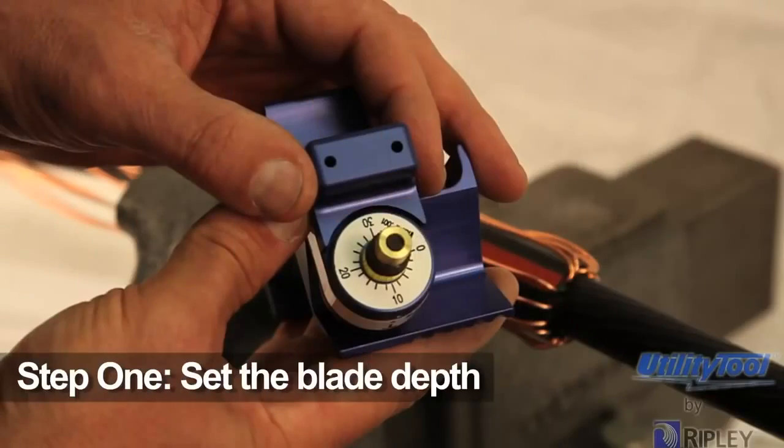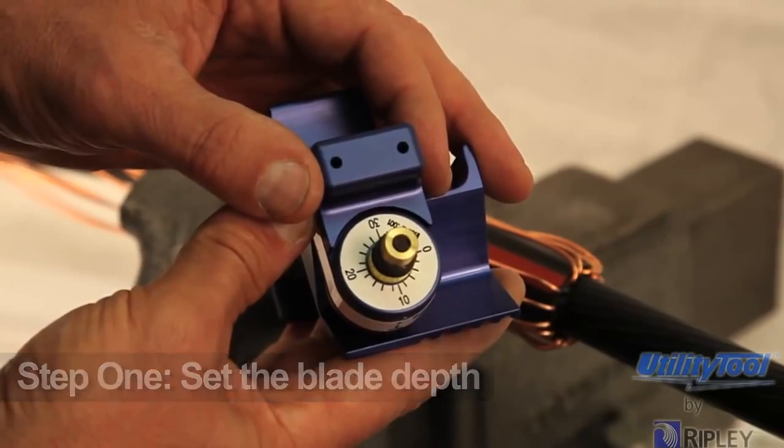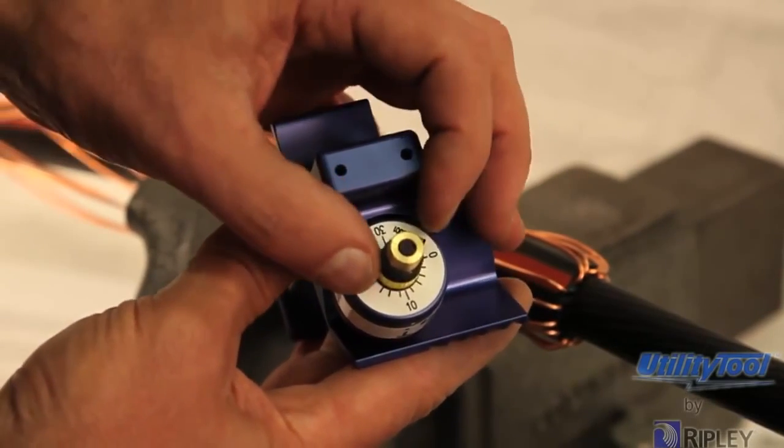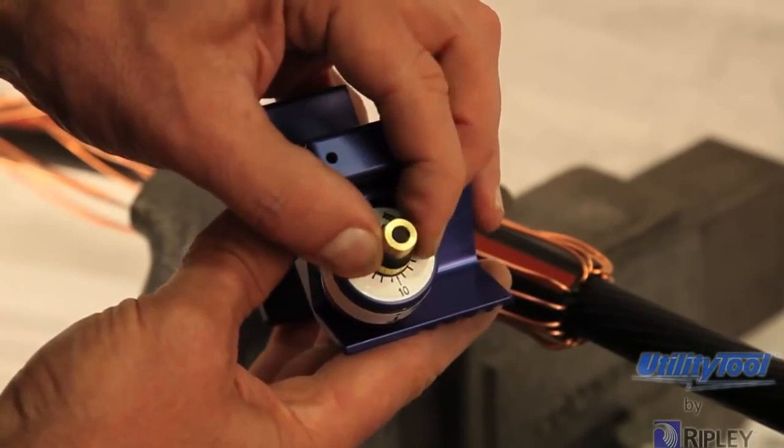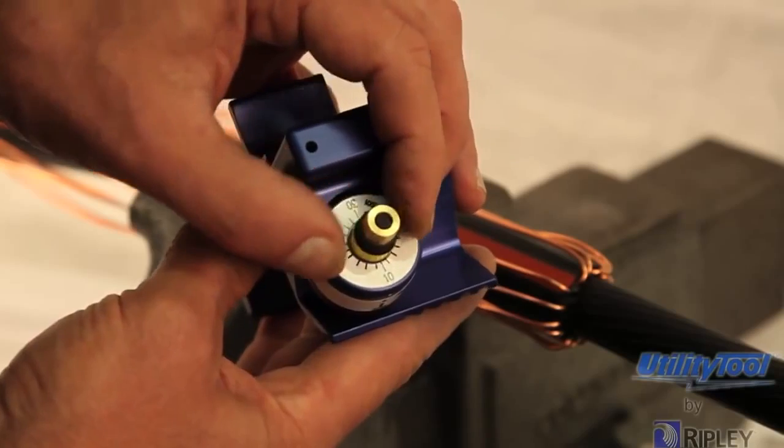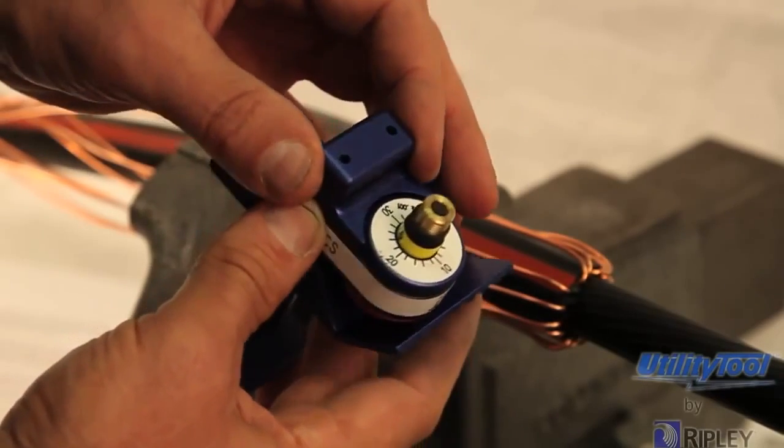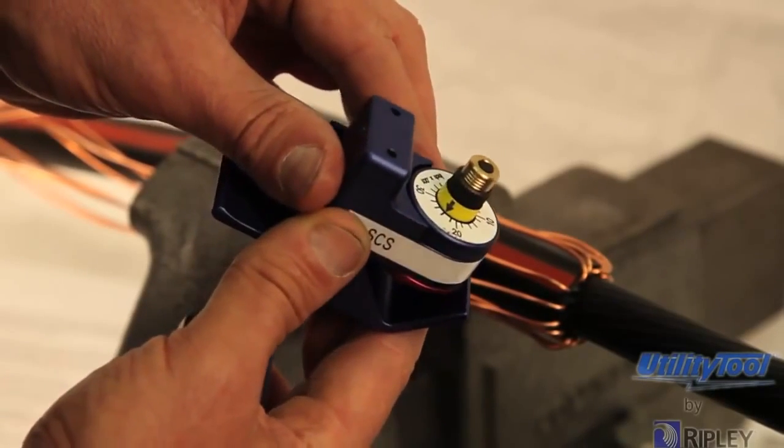Step 1. To begin using the SCS, set the blade to a depth equal to 75 to 90 percent of the thickness of the Semicon screen. To do this, rotate the blade adjustment knob clockwise until the arrow aligns with the desired blade depth. Always ensure that the blade depth is not more than the Semicon thickness.